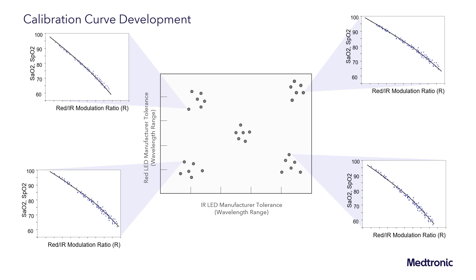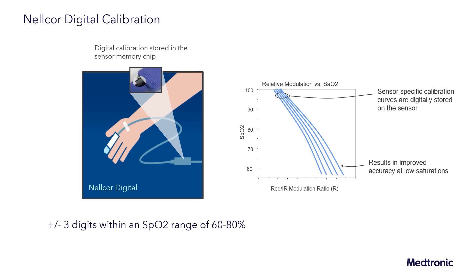In that method, we build up a transfer function so that we can calculate what the correct calibration coefficient should be for that wavelength combination of the sensor. What we can see then is that we have a method to convert our measured LED wavelengths at manufacturing to unique calibration curves. We employ this with Nellcor's digital calibration. Here, a digital calibration is stored or programmed onto the memory chip, and that digital calibration is representative of the sensor's wavelengths — specifically their measured wavelengths at manufacturing. This allows us to calculate unique calibration curves, and by doing that we're able to see a dramatic improvement in performance at low saturations where those absorption coefficients change the most. We're able to achieve that plus or minus three digits of accuracy within that range of 60 to 80.